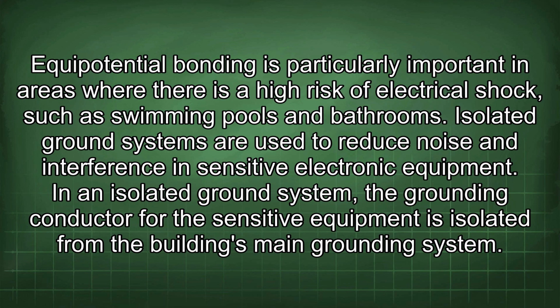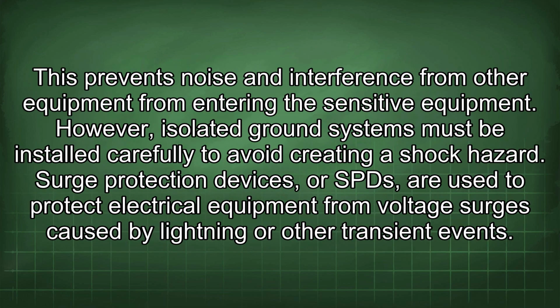Isolated ground systems are used to reduce noise and interference in sensitive electronic equipment. In an isolated ground system, the grounding conductor for the sensitive equipment is isolated from the building's main grounding system. This prevents noise and interference from other equipment from entering the sensitive equipment. However, isolated ground systems must be installed carefully to avoid creating a shock hazard.